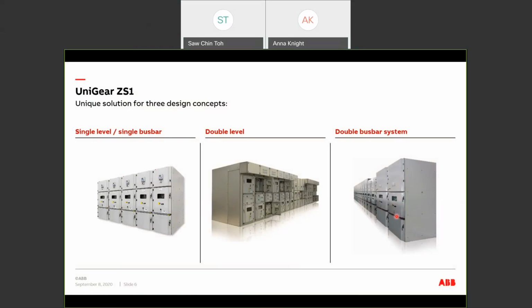UniGear panels cover a very wide range of application. We have the design for single bus bar, single level panel. This is the most popular range of product worldwide. For some market, mainly marine, for space saving, we have designed for double level. And the main product range for UniGear ZS1 also covers the double bus bar. This style of panels will provide increased redundancy to the system and is mainly used by utilities where service continuity is important.